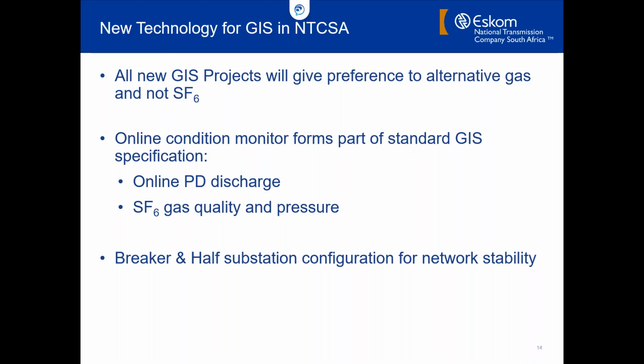Then the normal things we've gained experience on in the past include online partial discharge monitoring, which we're going to implement there, as well as SF6 gas quality and pressure online monitoring, because it's critical to keep your pressure at the desired or designed level in order to ensure you don't have insulation breakdown, which would lead to a failure.